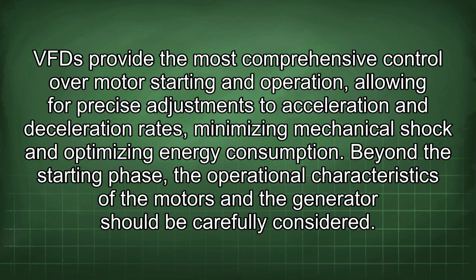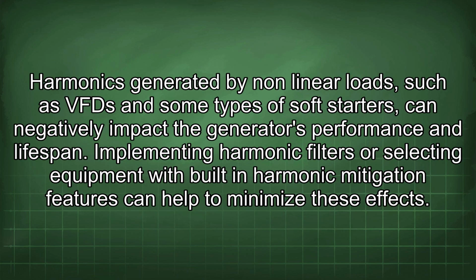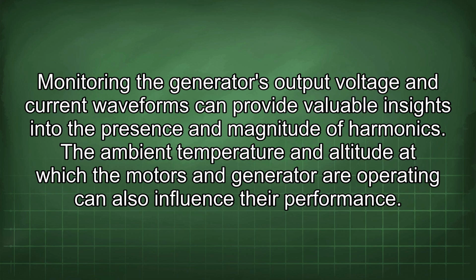Beyond the starting phase, the operational characteristics of the motors and the generators should be carefully considered. Harmonics generated by nonlinear loads, such as VFDs and some types of soft starters, can negatively impact the generator's performance and lifespan. Implementing harmonic filters or selecting equipment with built-in harmonic mitigation features can help to minimize these effects. Monitoring the generator's output voltage and current waveforms can provide valuable insights into the presence and magnitude of harmonics.